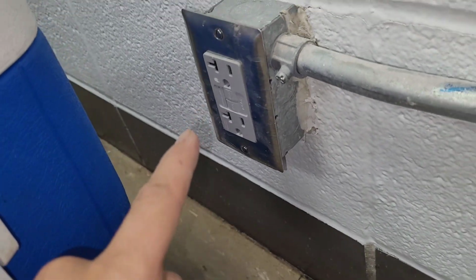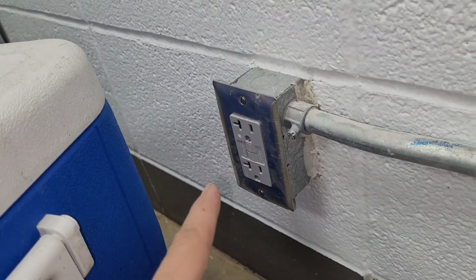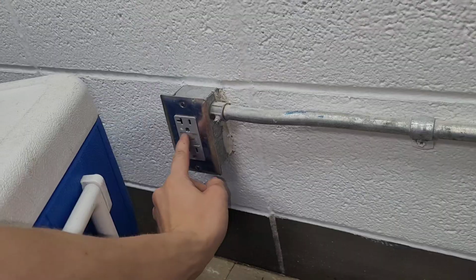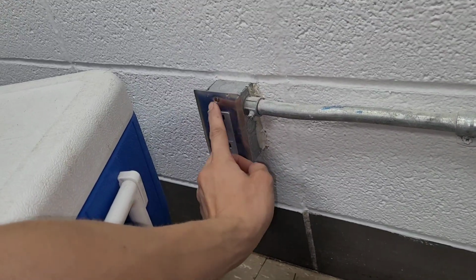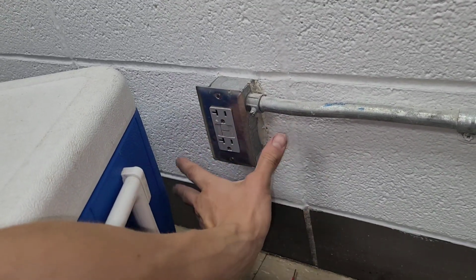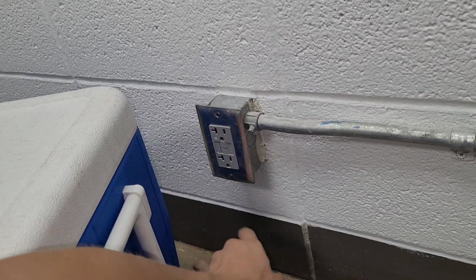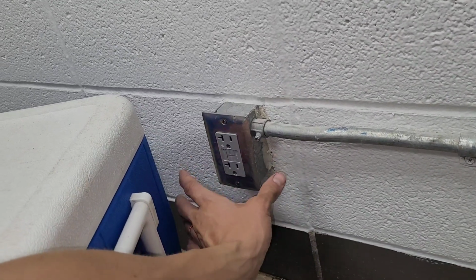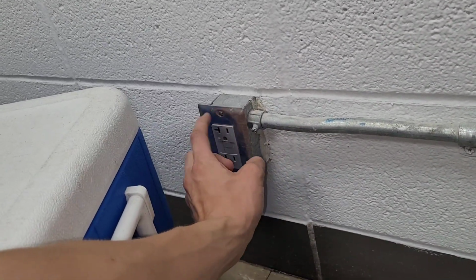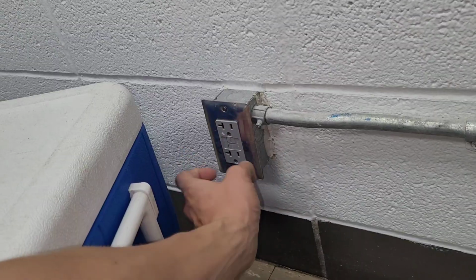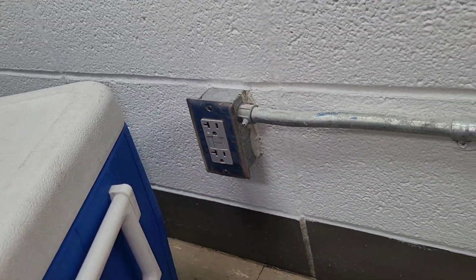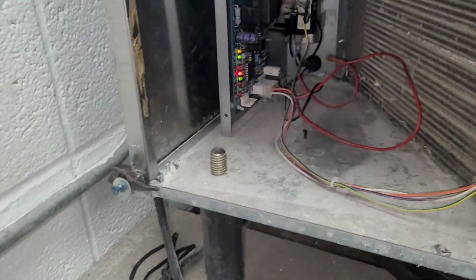But then the other thing he said was, is it being fed by a GFCI receptacle? Which it definitely is - this GFCI protects that outlet right up there. He said they actually do not recommend running it on a GFCI outlet, as that can give grounding problems with the equipment. If by code it's required, they recommend running a GFCI breaker because it's a little higher quality, but they said specifically the GFCI outlets can cause issues.